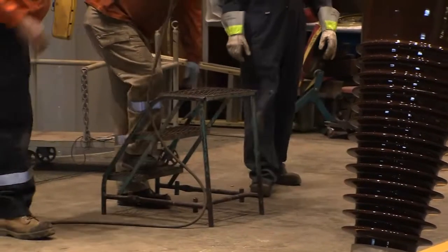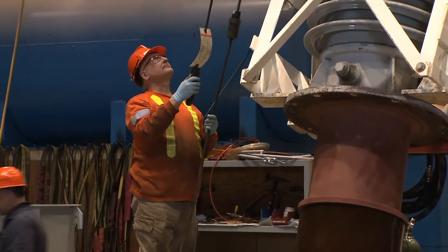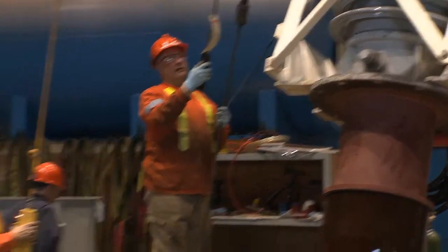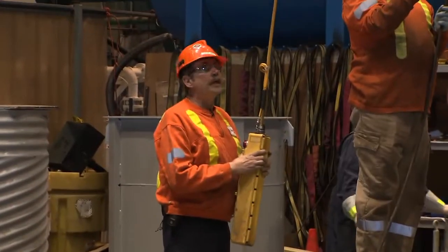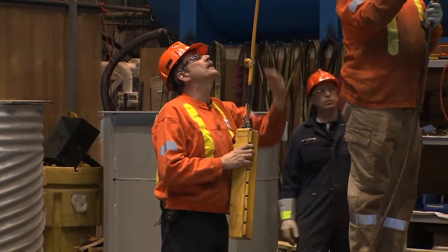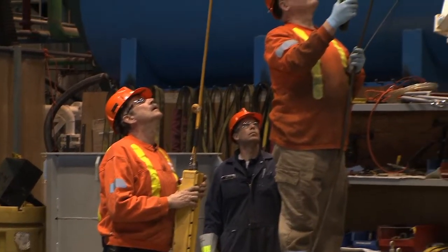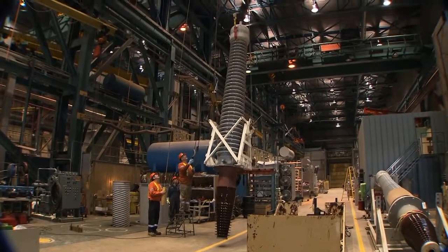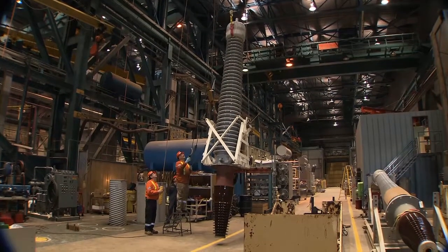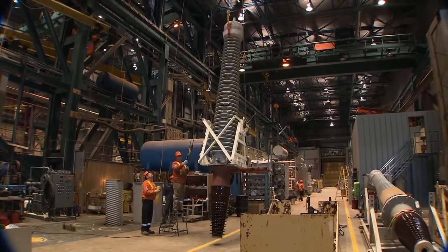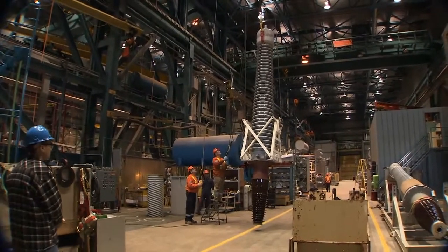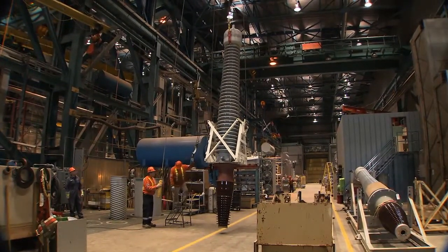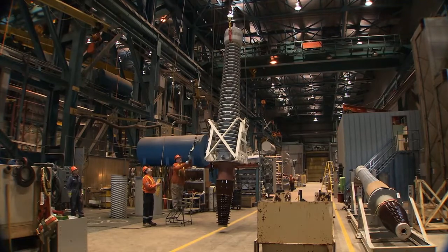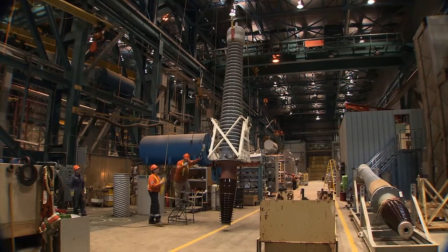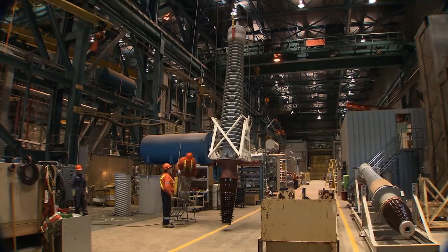Depending on the size of the bushing, as it is being raised and becomes higher off the ground, the team member controlling the electric hoist may need to stand on a small set of stairs to be able to control the remote. Once on the stool, the team member can operate the hoisting device and adjust the bushing's position. Okay, stop. Stop. That's pretty darn good, I think. The bushing should be stood up as straight as possible, so it can be placed in the hole with no difficulties. Perfect.